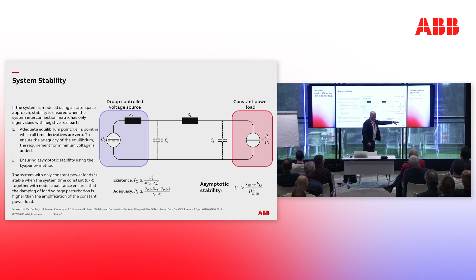Essentially, this simple rule tells us, first, whether this equilibrium of the system exists. Does the system reach an equilibrium? Second, because we talk about minimum voltage, it tells us this gives an adequate equilibrium. Why adequate? Because if you just blindly applied the math, your equilibrium could be at 0 volts. The system doesn't oscillate, but it's just not very practical. That's why it's important to also consider the equilibrium at the minimum voltage where the load will not disconnect.